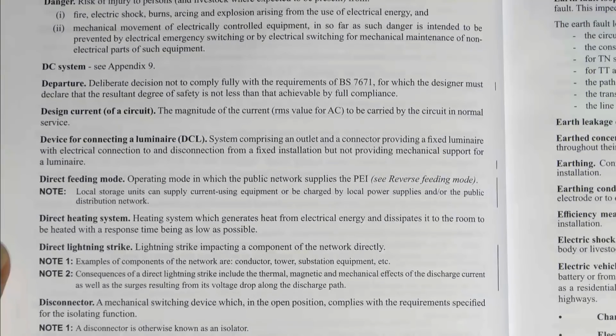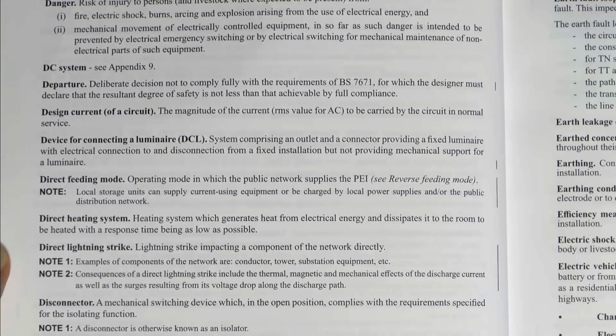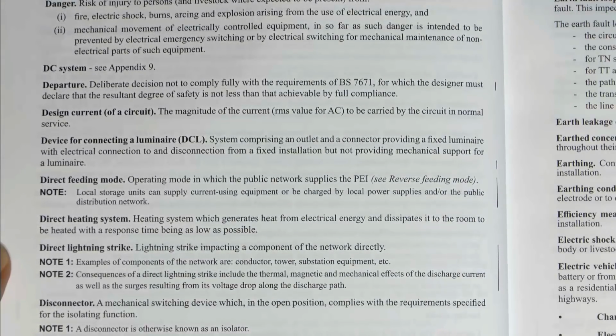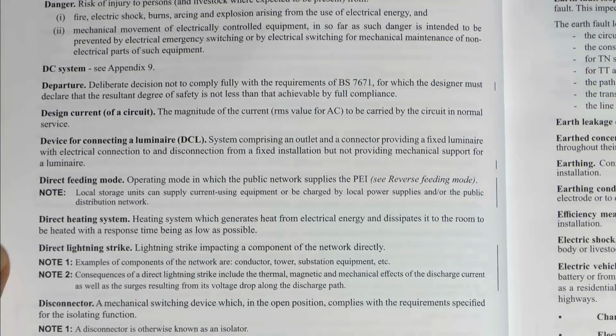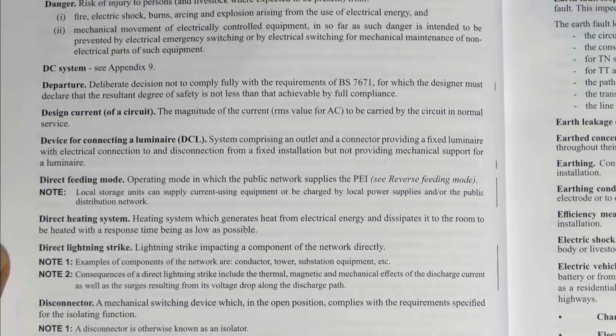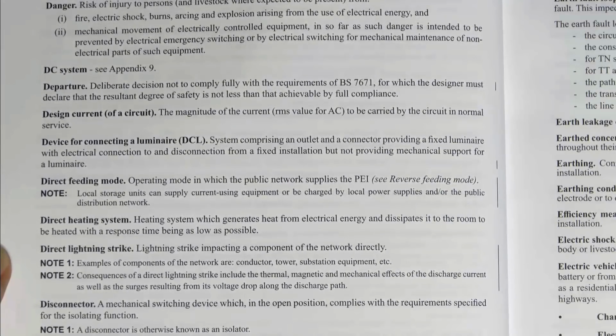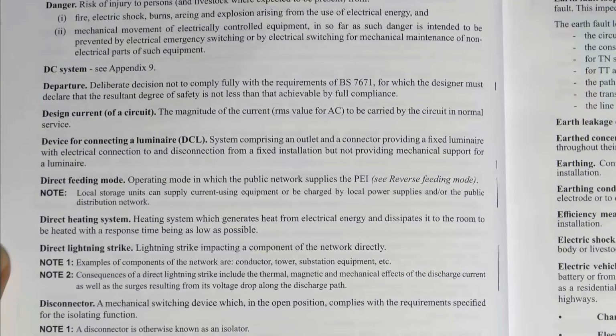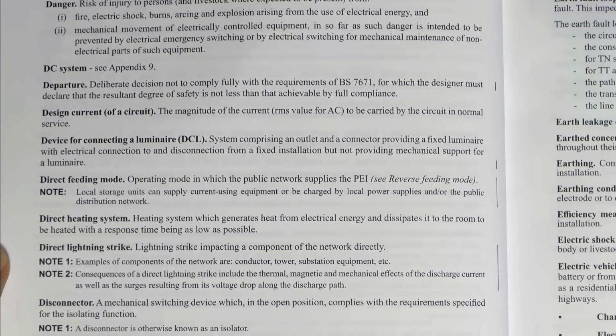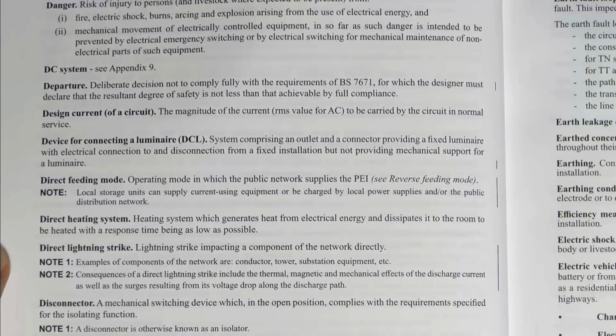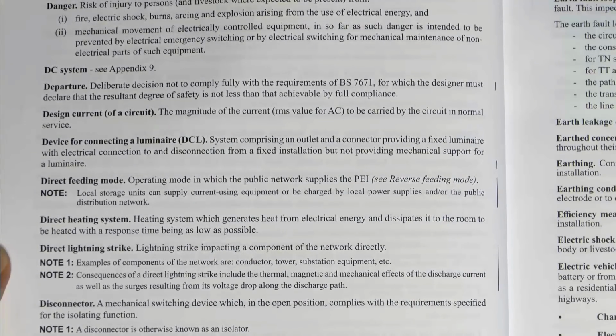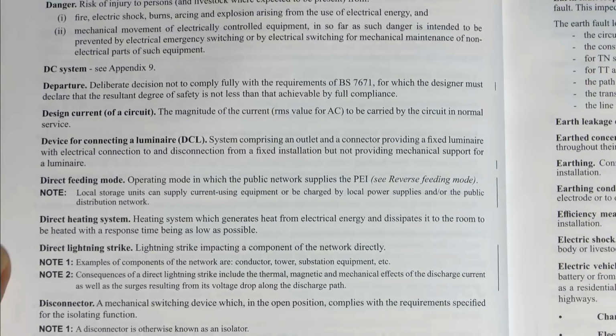And we've also got direct lightning strike - a lightning strike impacting a component of the network directly. Examples of components of the network are conductor, tower, substation, equipment, etc. Consequences of a direct lightning strike include the thermal, magnetic and mechanical effects of the discharge current, as well as surges resulting from its voltage drop along the discharge path. So this is where you've got lightning strikes on, say, a substation or transformer, causing a large voltage disturbance on the network and various other methods of damage as well. So that's now defined.